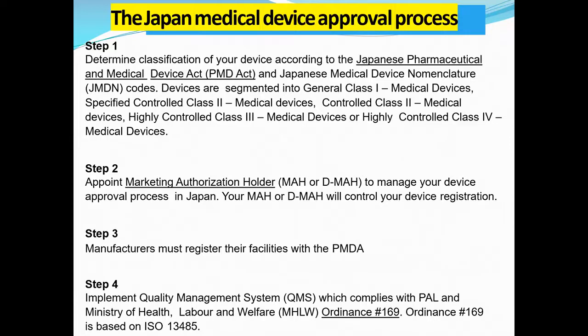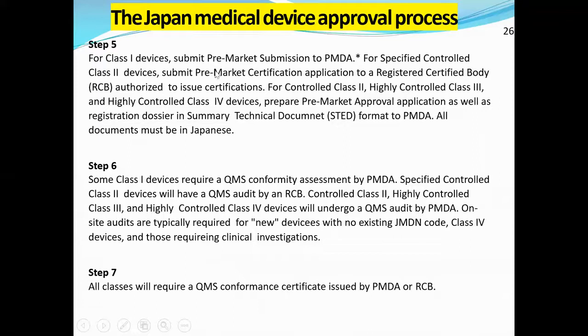Then implement a quality management system which complies with the PAL and the Ministry of Health, Labour and Welfare, that is MHLW, Ordinance number 169, which is based on ISO standards. Then for class 1 devices, submit a pre-market submission to PMDA. For specified controlled class 2, submit a pre-market certification application to a registered certified body, that is RCB, authorized to issue certification. For controlled class 2, highly controlled class 3 and highly controlled class 4 devices, prepare a pre-market approval application as well as a registration dossier in summary technical document, that is STED format, to PMDA, and all documents must be in Japanese.